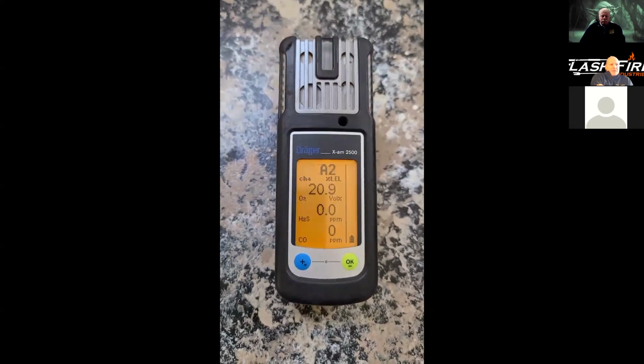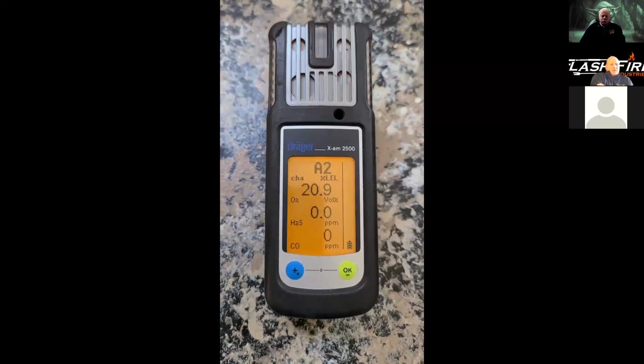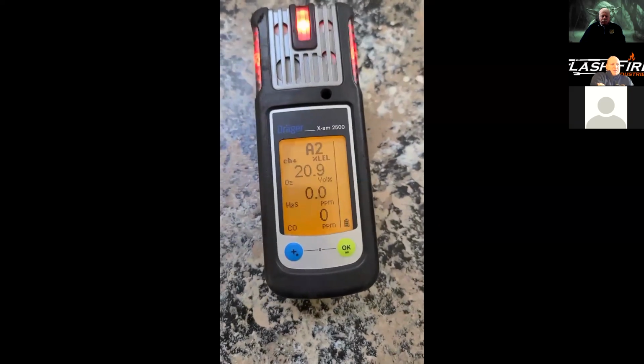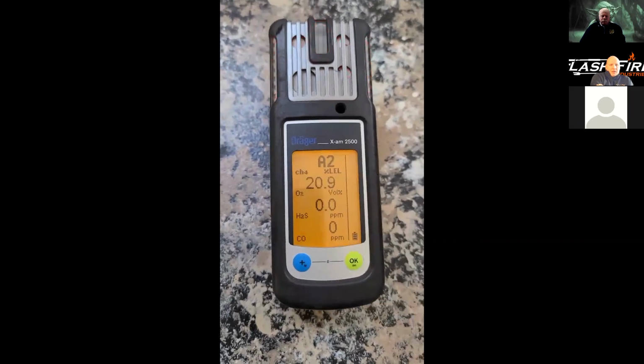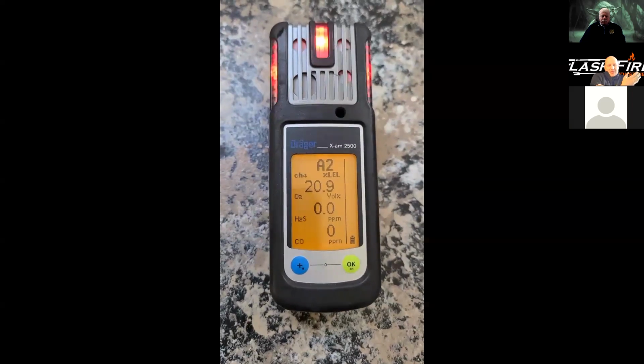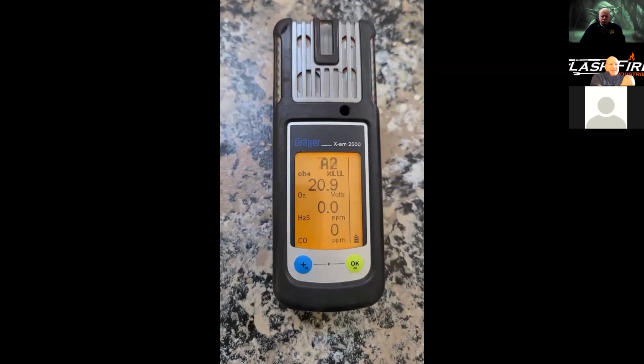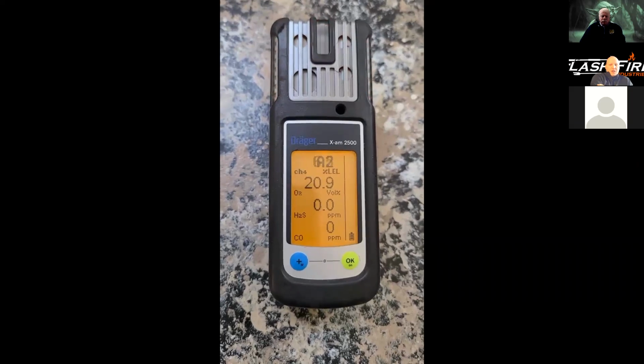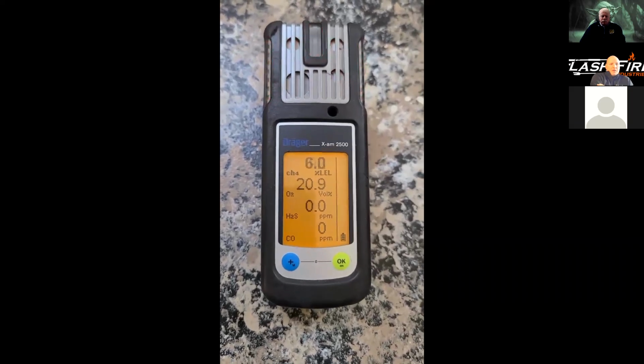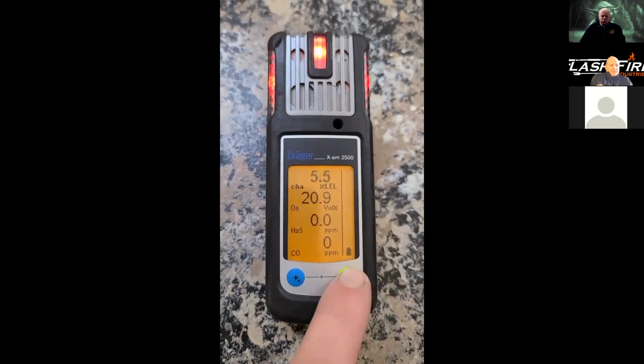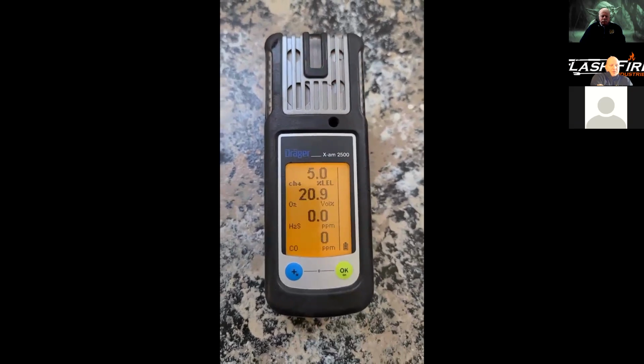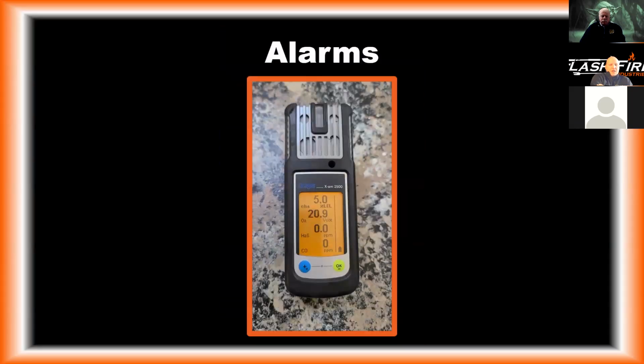So it goes into the high alarm, and then I'm going to let it drop back down. You're going to see that it drops into the low alarm, and then I don't remember how low it goes, but yeah, now I'm below the low alarm, but I'm still in high alarm because I have not acknowledged it yet. It wants to know, hey, alarm one, using that high alarm. So now I silence it. Okay. So that's the difference between a latching and a non-latching alarm. Latching, you need to acknowledge it even if you drop down. Non-latching, you do not need to.